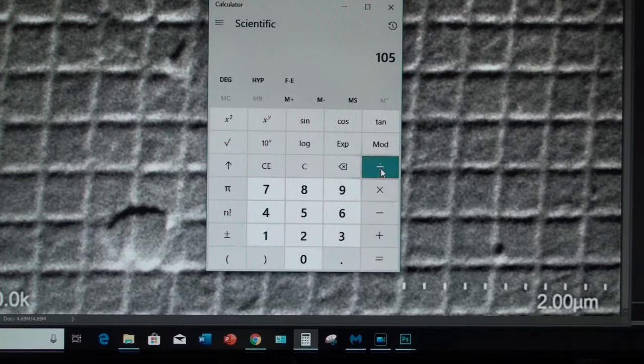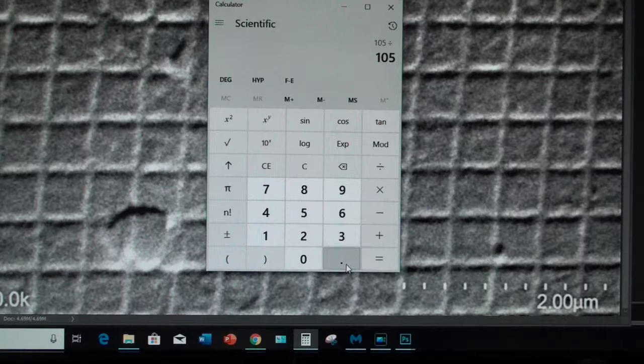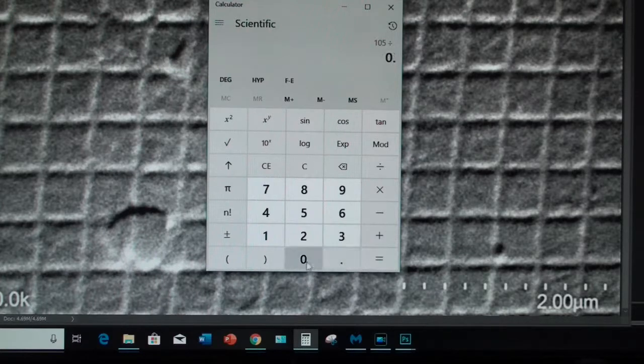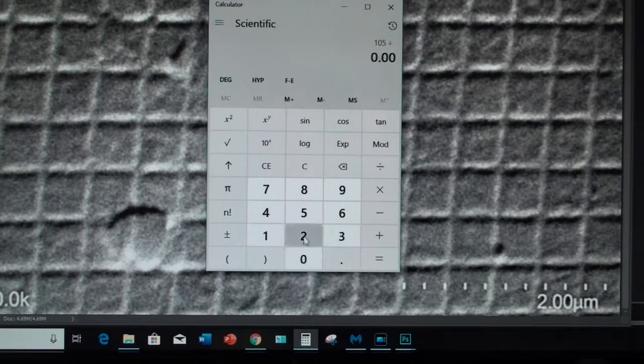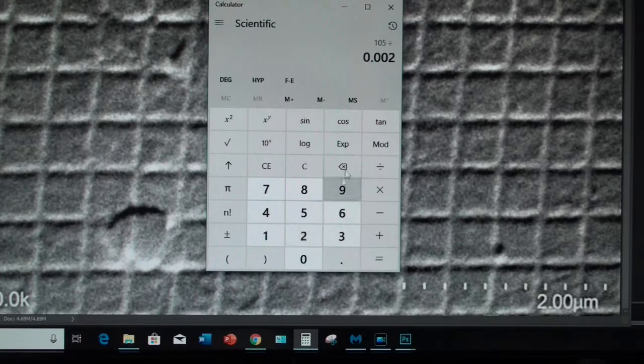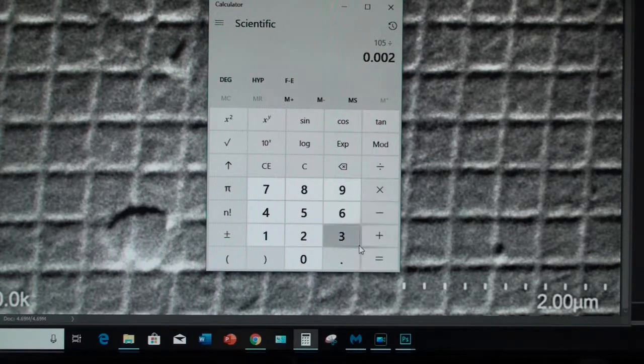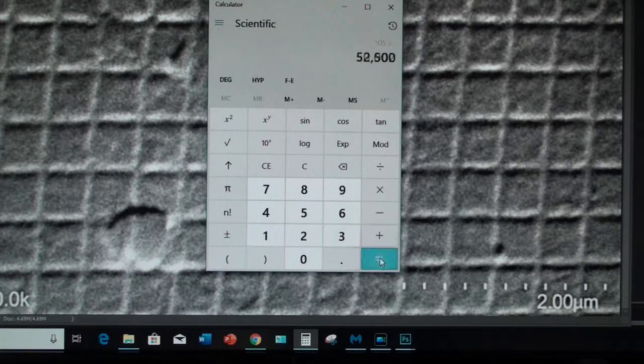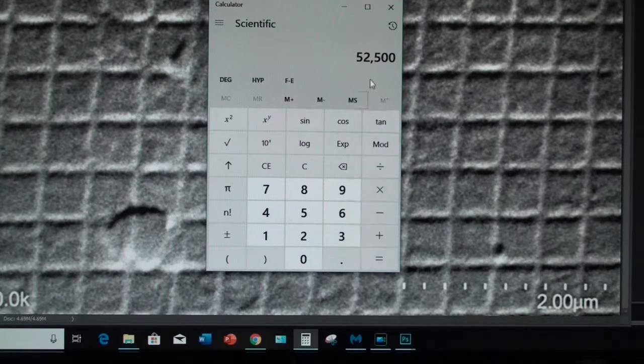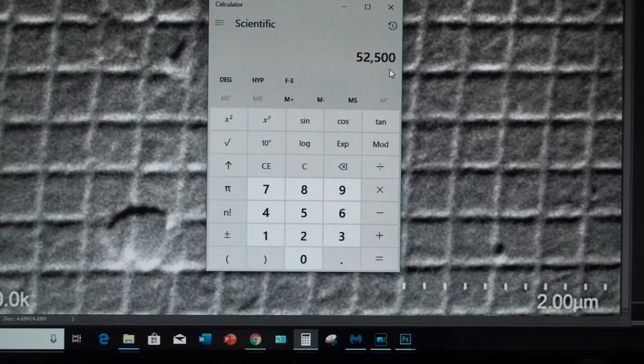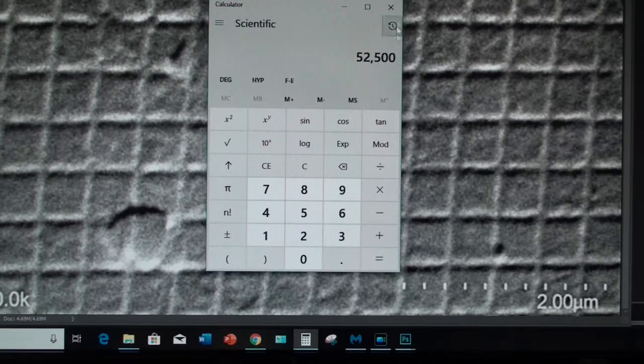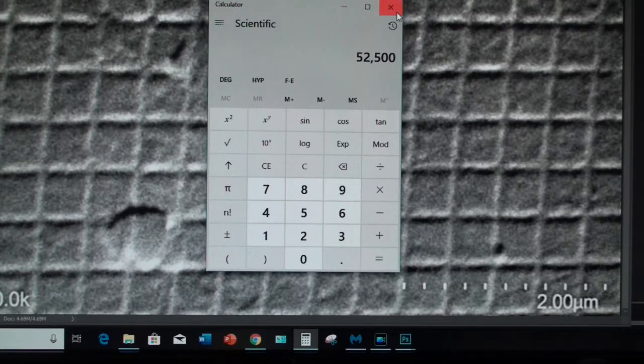And I'm going to divide that by the indicated magnification of 2 microns. And so I'm using 0.002 millimeters. I could have done 105,000 microns divided by 2. And I would have gotten the same number of 52,500 magnification.